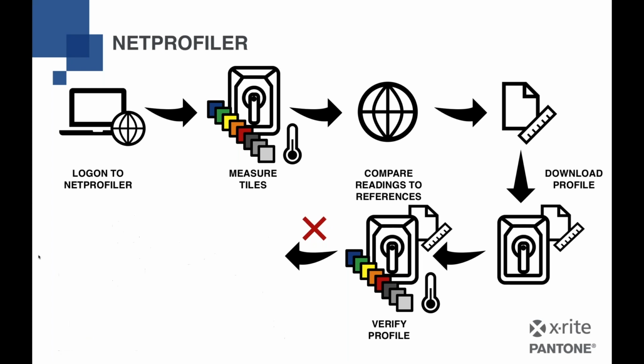But if your results on the NetProfiler verification run bad, then of course you know your instrument does not perform properly any longer, and then of course you should first diagnose. You should diagnose whether your instrument is in a clean and stable condition, whether your white tile and black trap are in a clean and stable condition, whether all these tiles of the NetProfiler tile set are in good condition, whether you had any environmental changes of massive nature, like a 10-degree Fahrenheit or 7-8 degrees Celsius temperature shift or something like that, which happens occasionally.